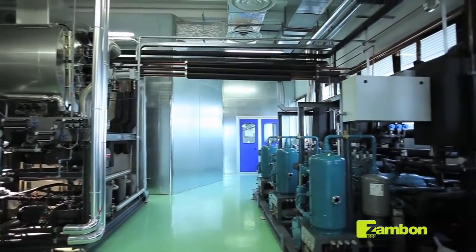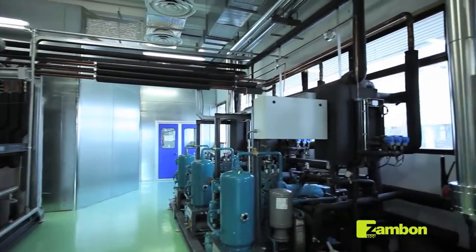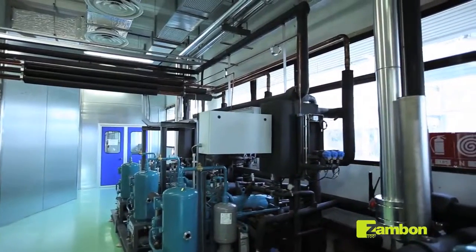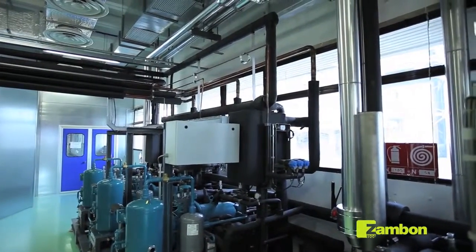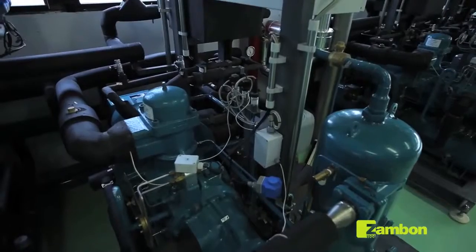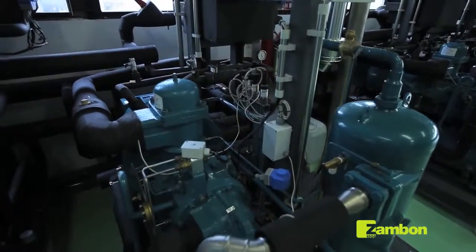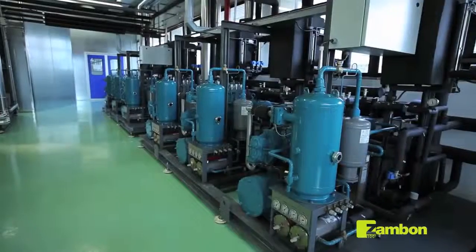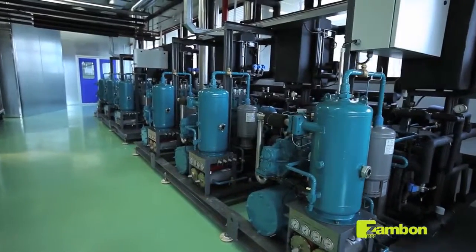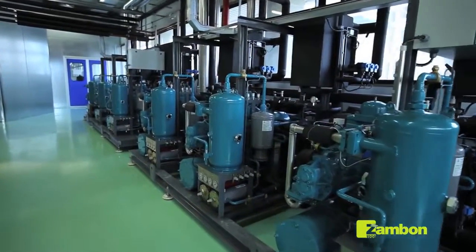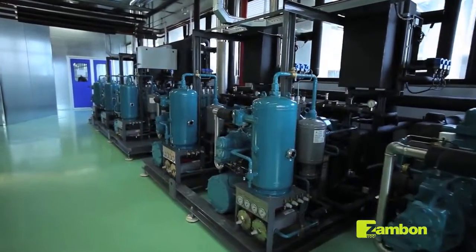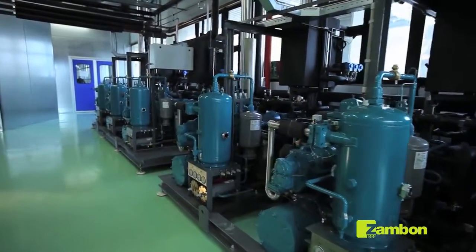Freezing. The product is frozen by reducing the temperature of the shelves thanks to a sophisticated cooling unit linked to it. Primary drying. The pressure is reduced and the temperature of the shelves increased. Secondary drying. The pressure of the chamber is reduced and the temperature of the shelves increased.